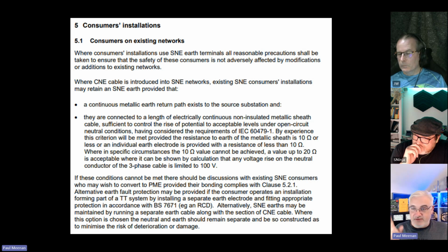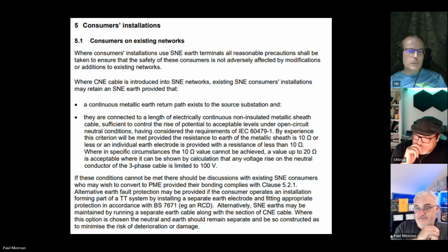Where in specific circumstances the 10 ohms value cannot be achieved, a value up to 20 ohms is acceptable, which comes from BS 7430. It is acceptable where it can be shown by calculation that any voltage rise on the neutral of a three-phase cable is limited to 100 volts. What's your thoughts on that? Because I know what my thoughts are. I've got a lot of questions on that one.